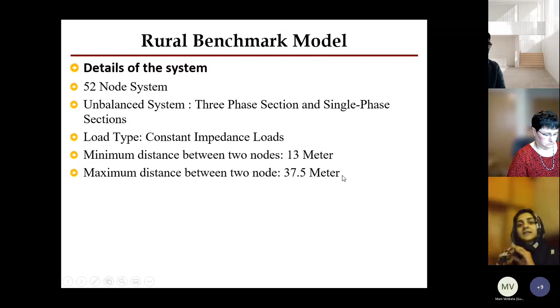This is a small system for a rural area in India. The transformer is rated 63 kVA, transforming from 11 kV to 433 volts. These are the impedance ratings, and the configuration, as with most transformers from substation to the lower level, is delta and Y grounded.